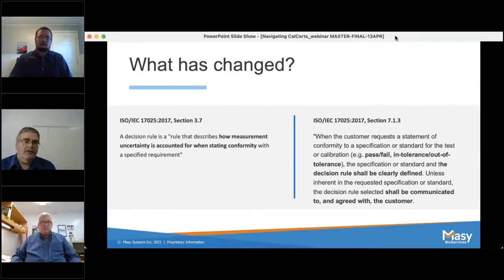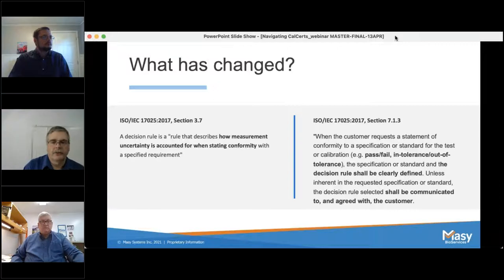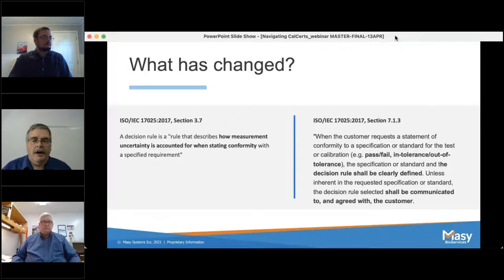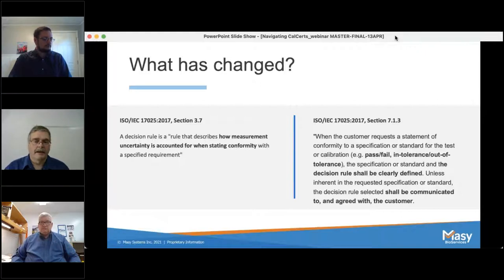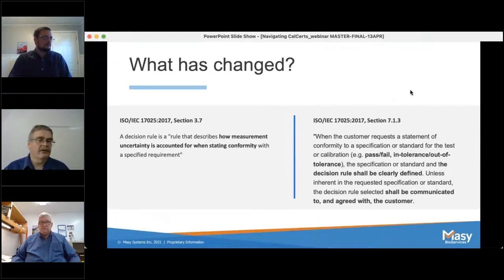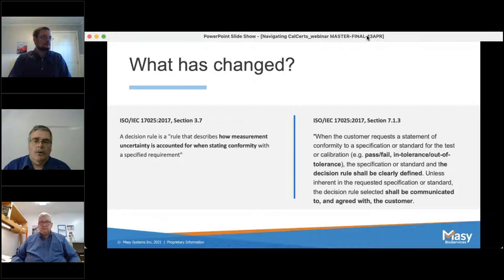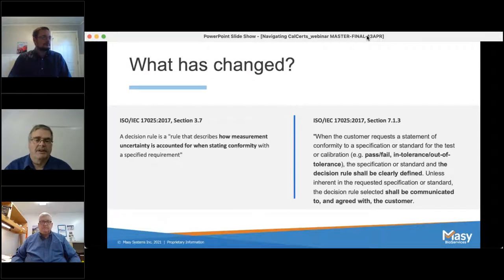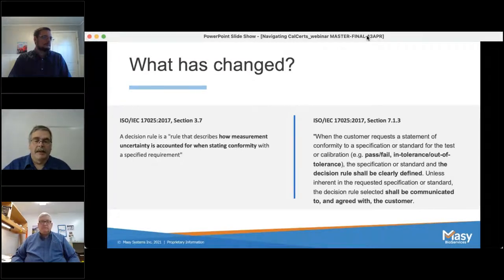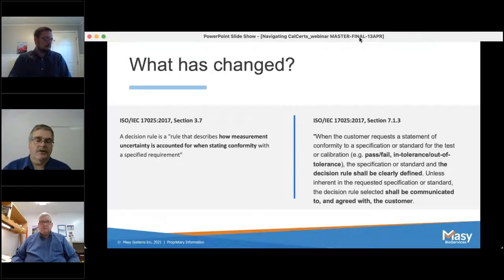What changed in the current version of 17025? In the previous version from 2005, there was a single sentence regarding measurement uncertainty and making a statement of compliance — something like pass/fail, in or out of tolerance. That 2005 version simply said: 'When statements of compliance are made, the uncertainty of measurement shall be taken into account.' That was it — one sentence. And honestly, most calibration houses ignored that sentence or made a blanket statement that uncertainty was not taken into account, which was the opposite of what the authors of the standard wanted to achieve.